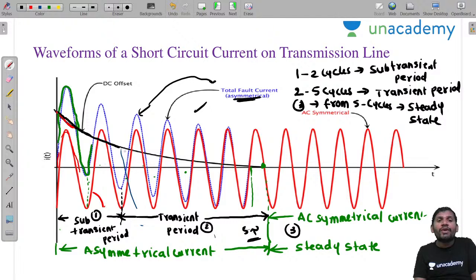Why do we get asymmetrical current? Because the DC offset current is added to the symmetrical AC component of current. Once this DC offset current falls to 0, we again get the symmetrical fault current, and this state is taken as the steady state.